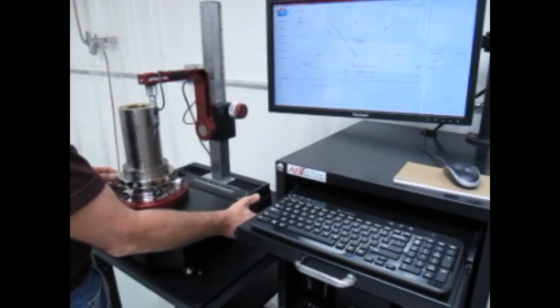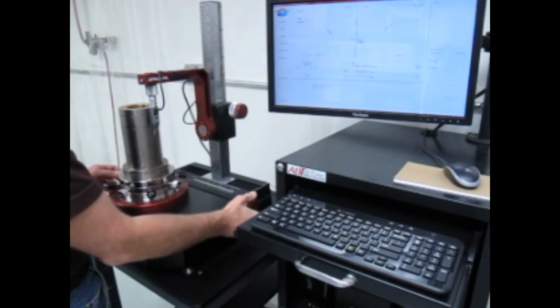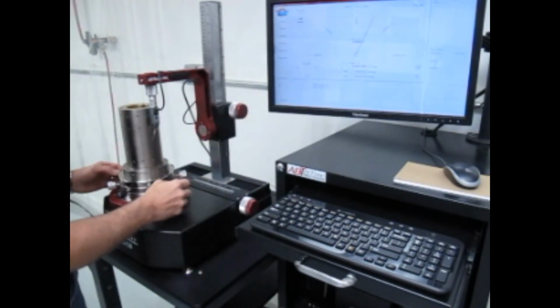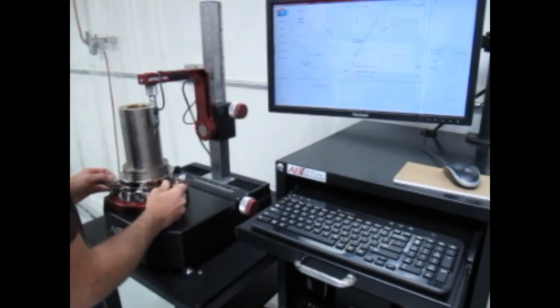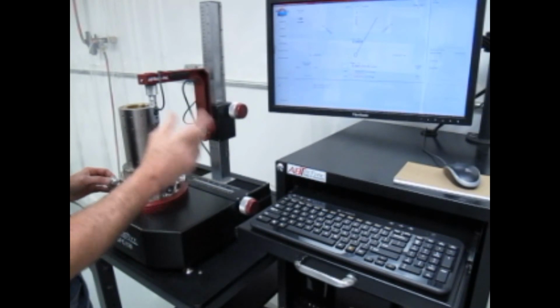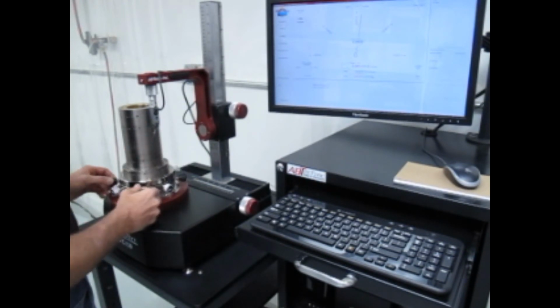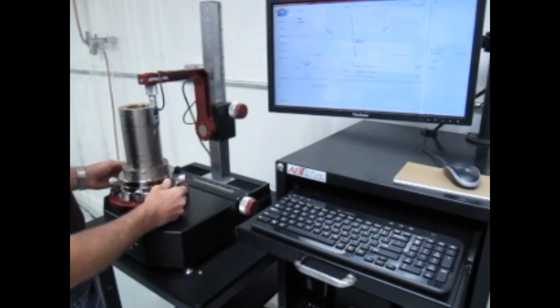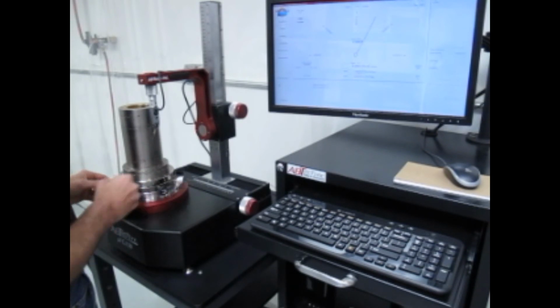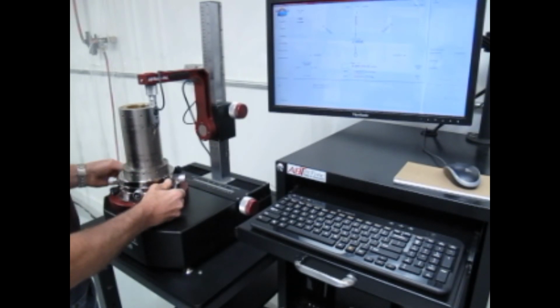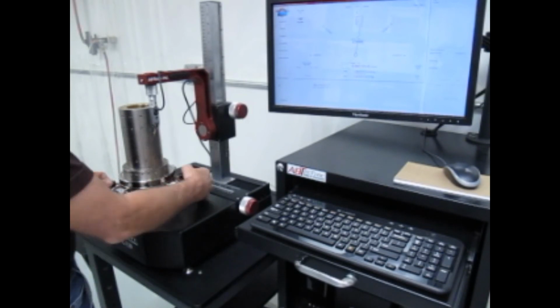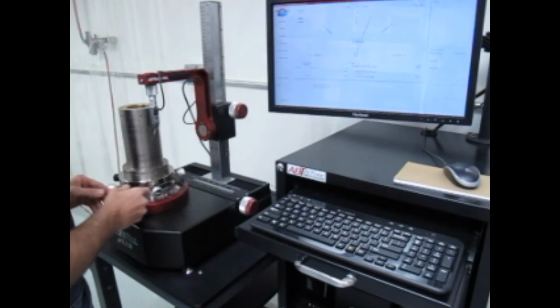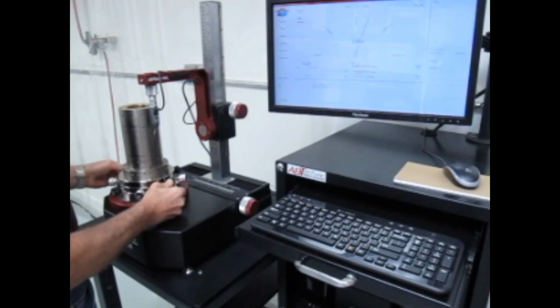What I can do is tweak that even further by changing to the medium scale, which is plus or minus a thou as opposed to plus or minus 10 thou. Now this is only taking a segment of the probe displacement, but it's magnifying that so that I can adjust it even more if I desire. So I'm going to find the high point, and again, with very fine resolution knobs here, take about half of that out, then I'm going to move 90 degrees and take half of that displacement out.